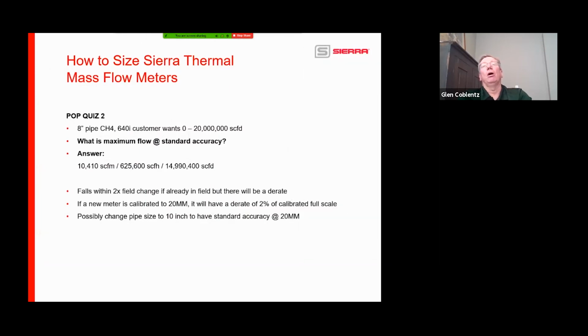Okay. All right. Well, the customer wanted 20 million. Okay. Oh, it's actually the correct unit of measure here. So this falls within the 2x field change if already in the field, but there will be a derate. If you remember, we talked about that's one of the powerful abilities of the 640i. You can increase the full scale flow rate. So if we wanted to, this is a very, very small increase. So you can easily increase the full scale to 20 million in the field.